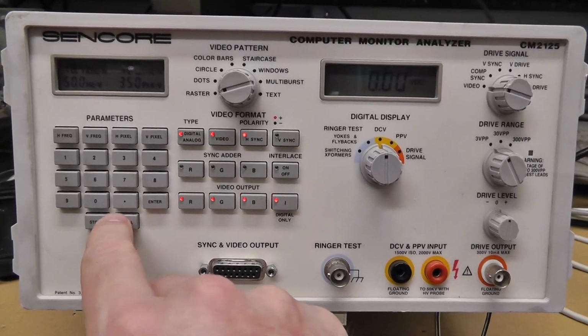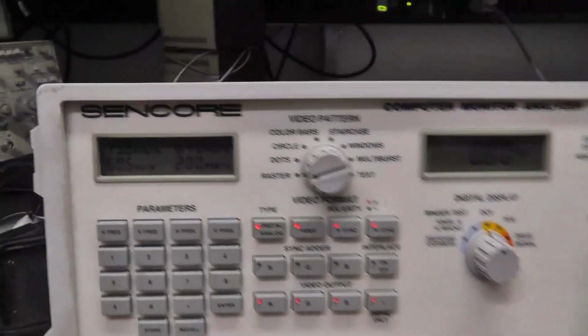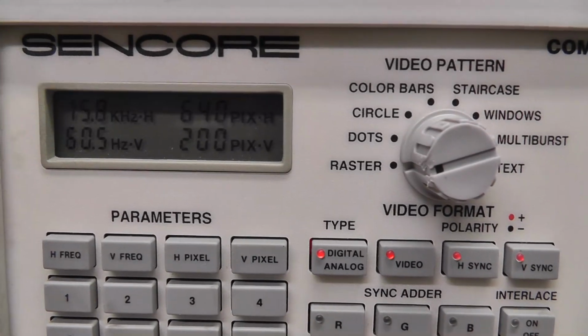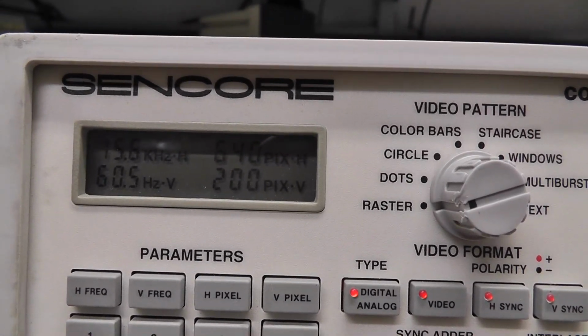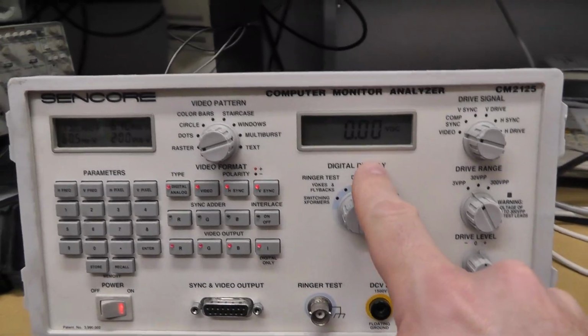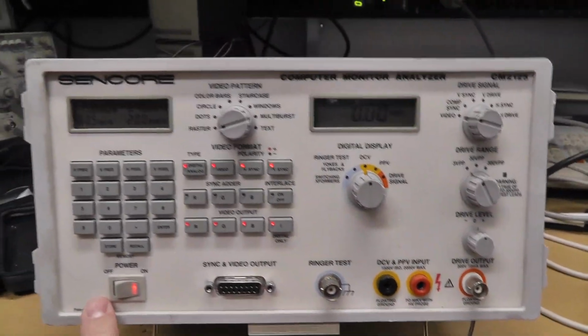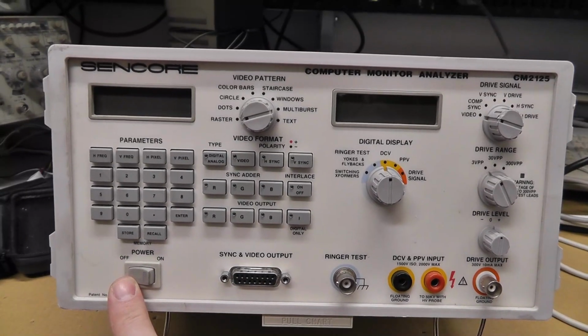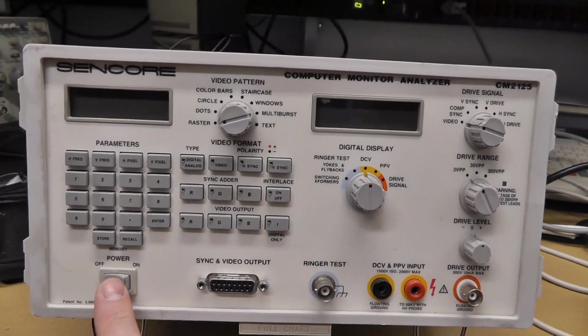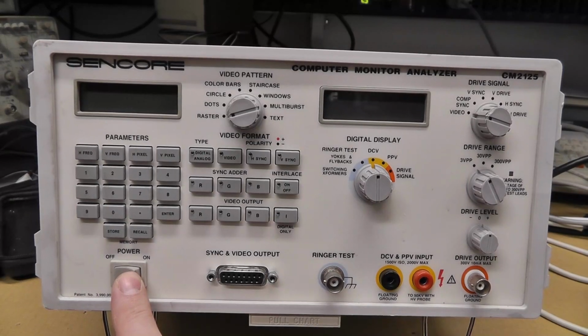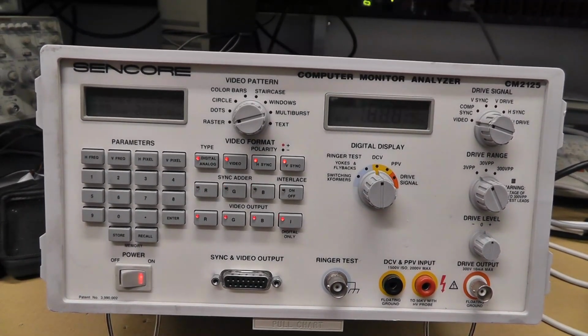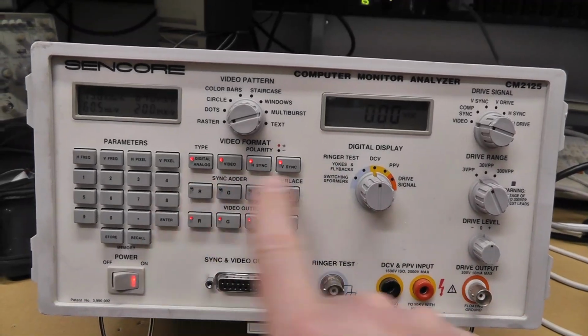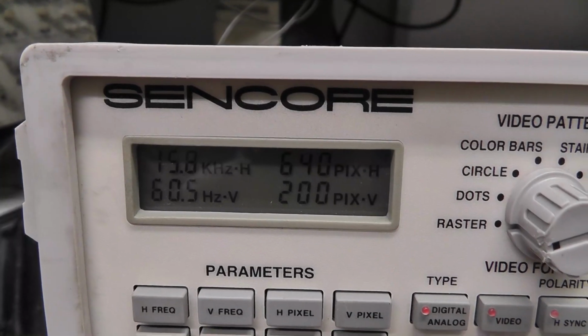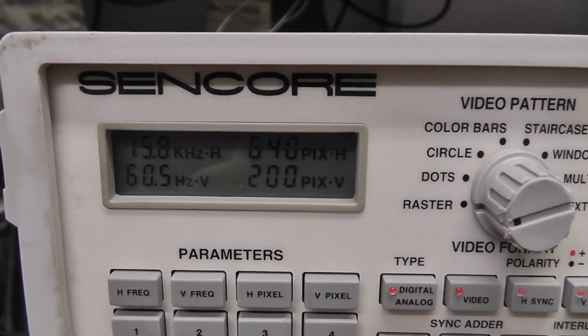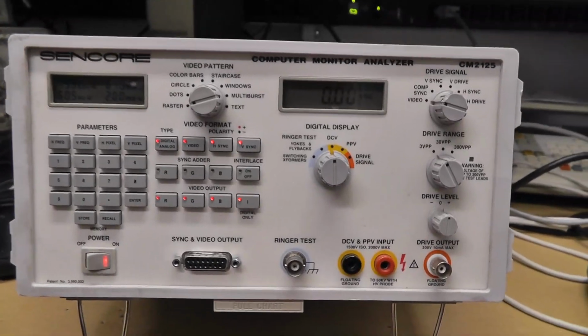All right, so let's do that again. Actually, let's do recall 0, enter, and we get 15.8, 640 pixels by 200, 60 hertz, and our digital display shows zeros. Let me power this off real quick, and it should come back to the last stored setting. Yeah, you see it goes do-do-do-do, and then it goes into the last setting it was at, which is 15.8, 640 by 200. All right, so that's the power-on test.